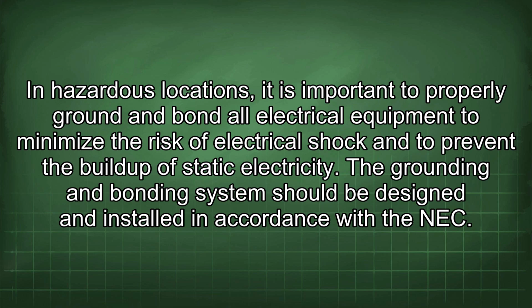Grounding and bonding systems are used to provide a low-impedance path for fault currents to return to the source. In hazardous locations, it is important to properly ground and bond all electrical equipment to minimize the risk of electrical shock and to prevent the buildup of static electricity. The grounding and bonding system should be designed and installed in accordance with the NEC.